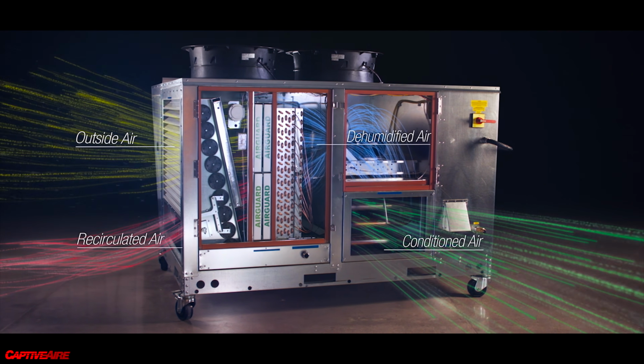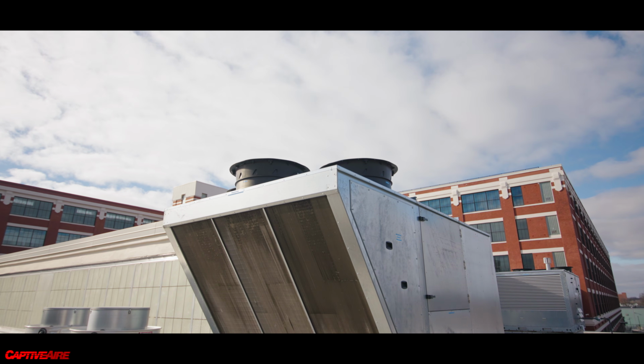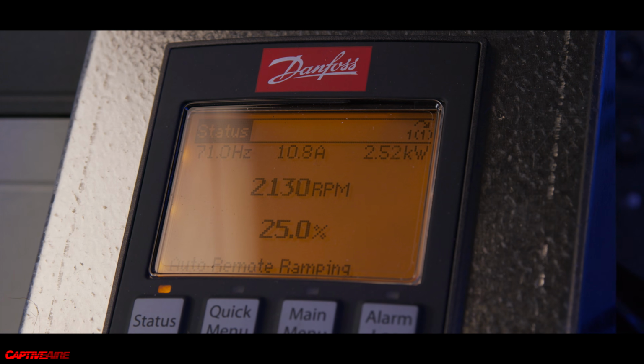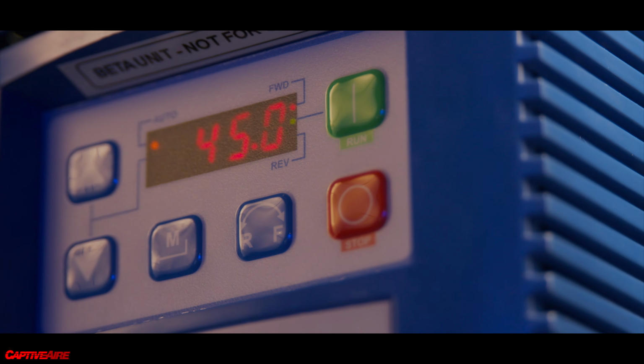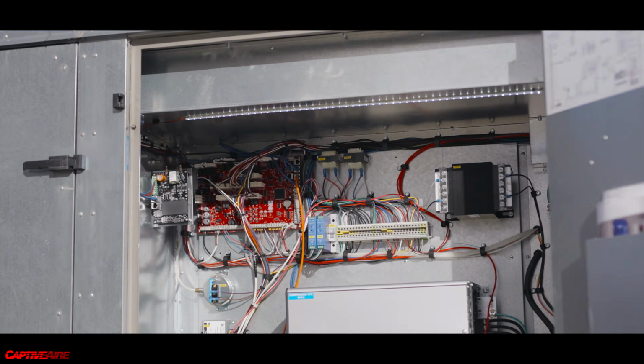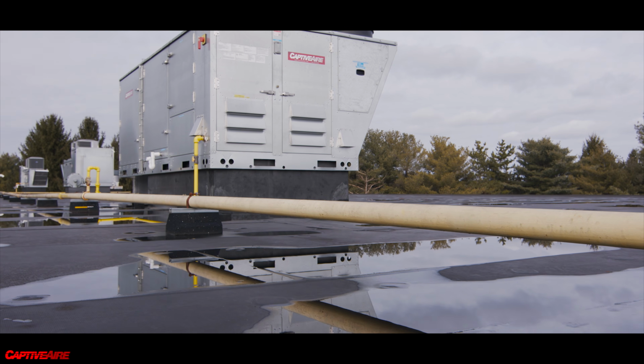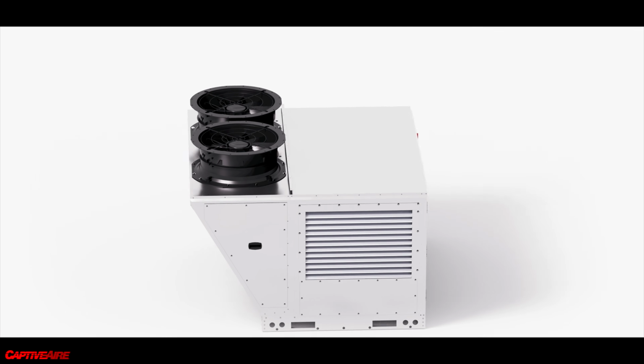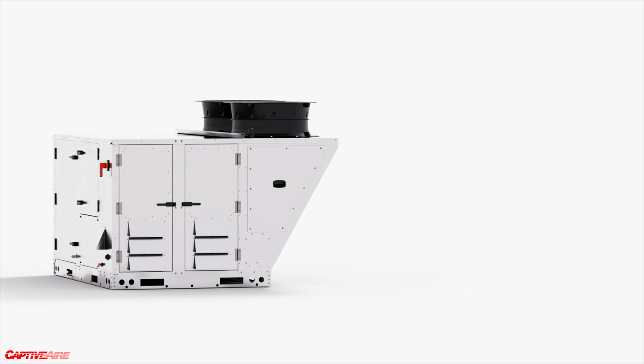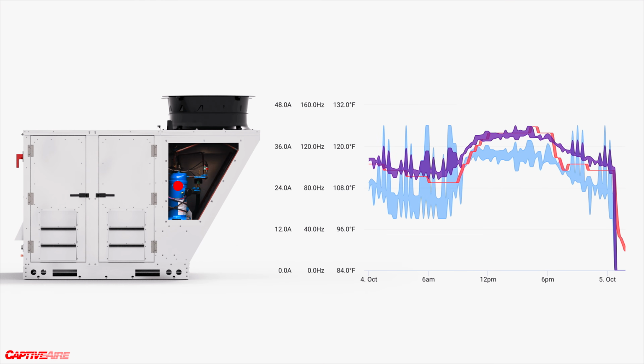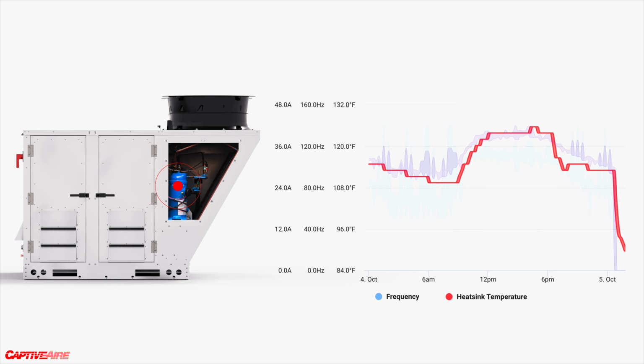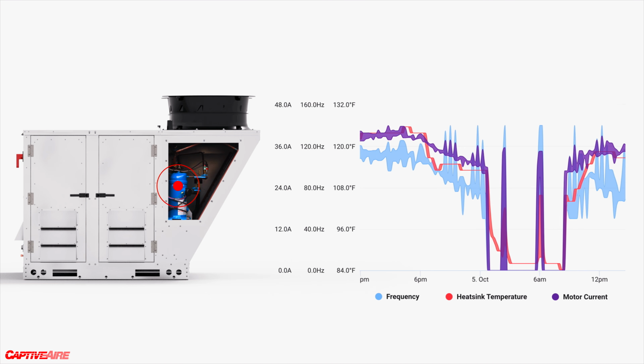But then from the controls standpoint, there are going to be challenges when you've got one piece of equipment that can do so many different things for so many different people. The key to this flexibility is really in the amount of modulation that's built into Paragon. And while the unit is perfectly capable of running all on its own, having a tool like CASLink ensures that each modulating component is precisely tuned for the application. So I want to show you just a few of these data points, starting with the variable speed compressor. We can see data regarding its speed, temperature, oil status, and more in real time, or we can even go back and see what it was doing, say, last year.